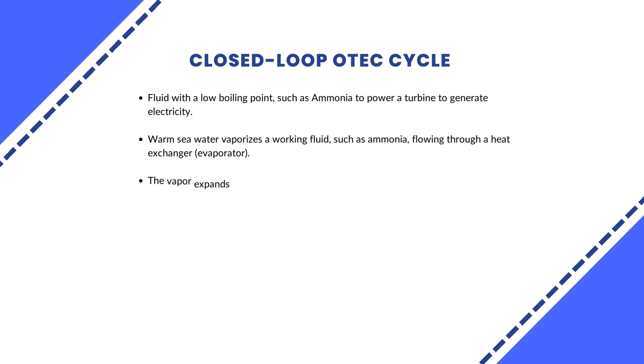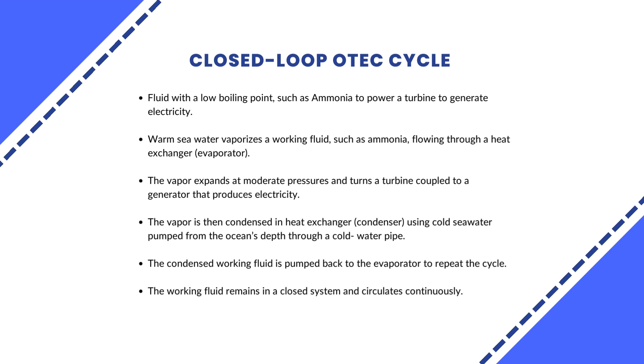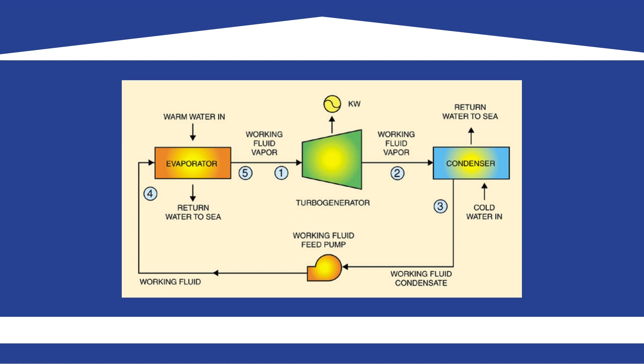Now we will discuss the closed loop OTEC cycle. In this particular operation, a fluid with a low boiling point such as ammonia is used to power a turbine to generate electricity. In the closed cycle system, warm sea water vaporizes a working fluid such as ammonia flowing through a heat exchanger or evaporator. The vapor expands at a moderate pressure and turns a turbine coupled to a generator that produces electricity. The vapor is then condensed in a heat exchanger or condenser using cold seawater pumped from the ocean's depth through a cold water pipe. The condensed working fluid is pumped back to the evaporator to repeat the cycle. The working fluid remains in a closed system and circulates continuously. The heat exchangers, which are the evaporator and condenser, are a large and crucial component of the closed cycle power plant, both in terms of actual size and capital cost.